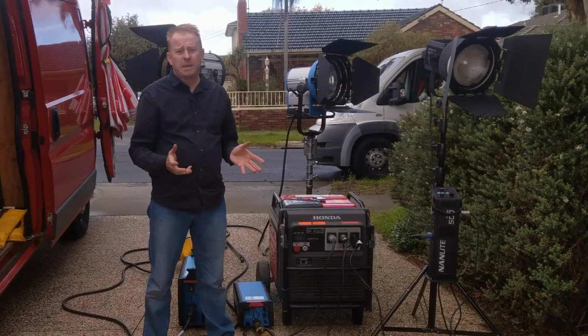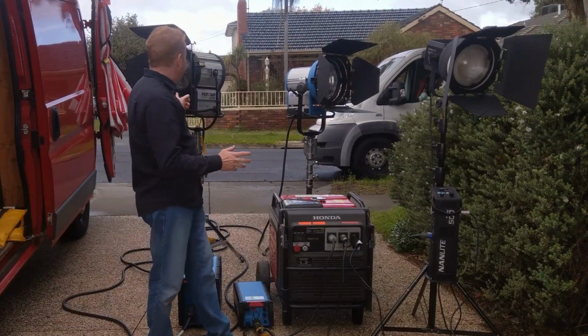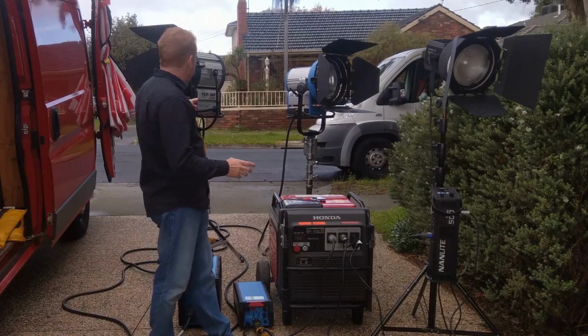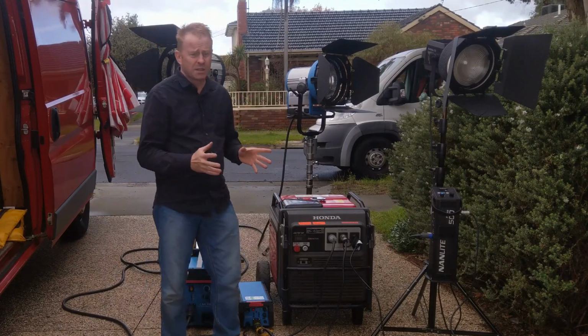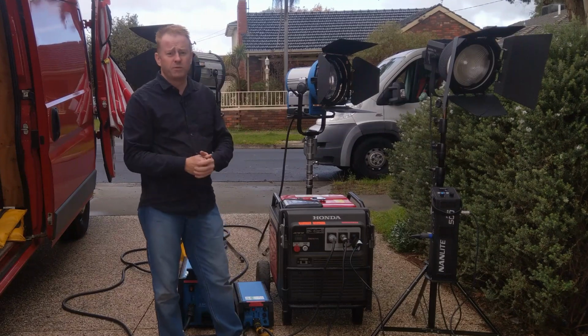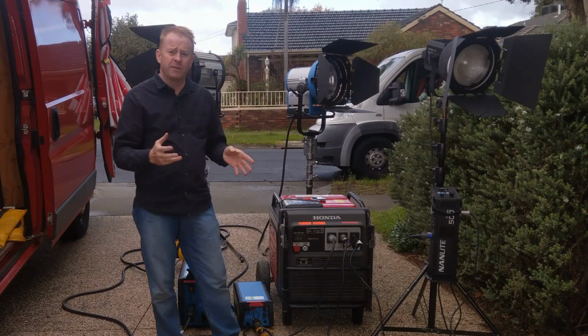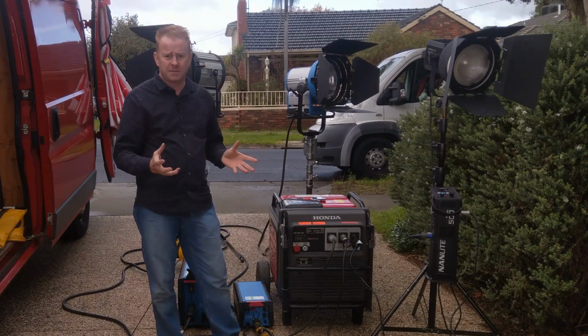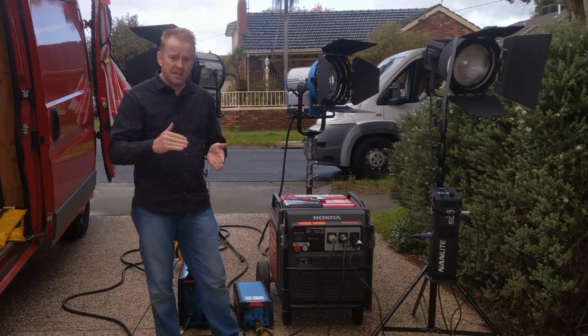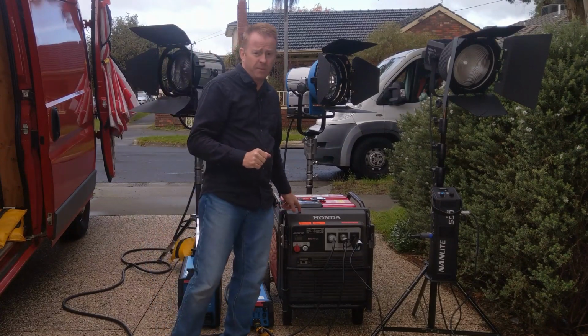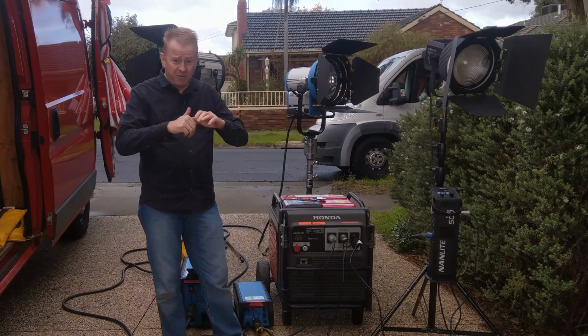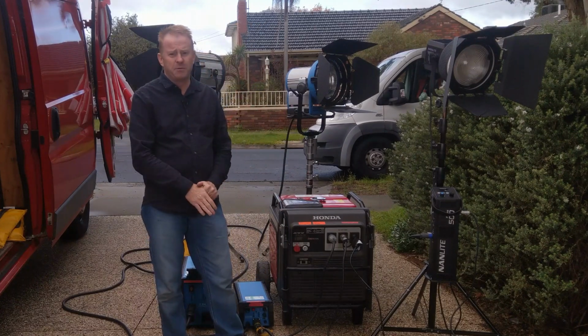Now here's where a lot of people go wrong. Okay, so at the moment I've got, what's this, 5.25 kilowatts of lights here, 5.25 kilowatts. And that's allowing for the power factor in the ballasts. All right, so that is under the constant load rating of the generator. Okay, so yep, no worries, can fire them all up. But here's what a lot of people forget.